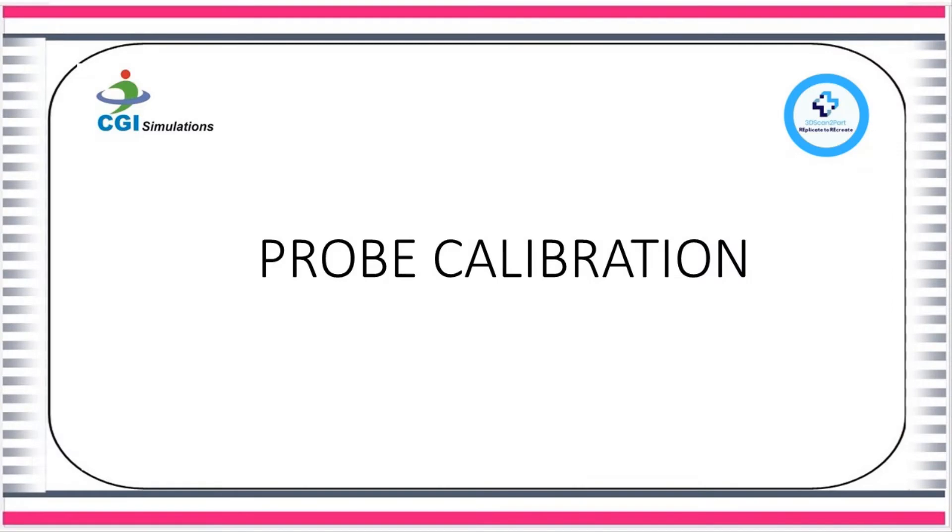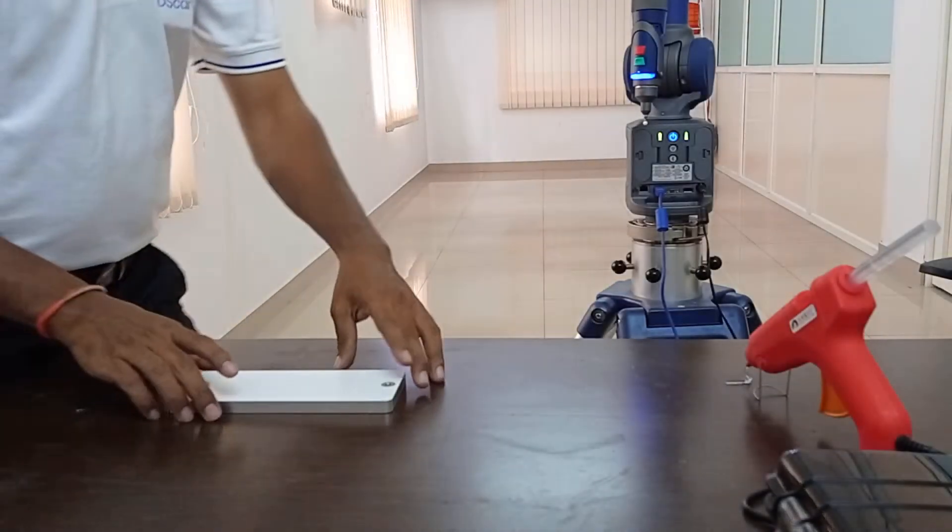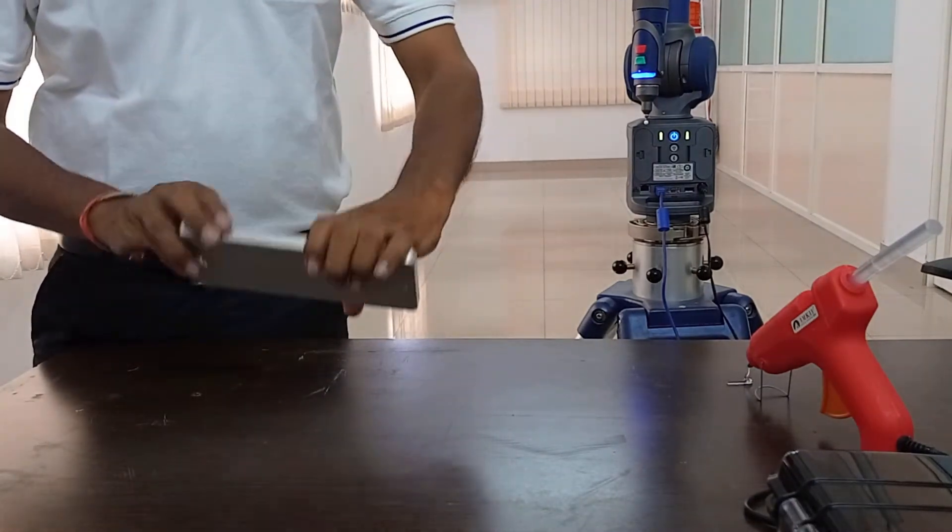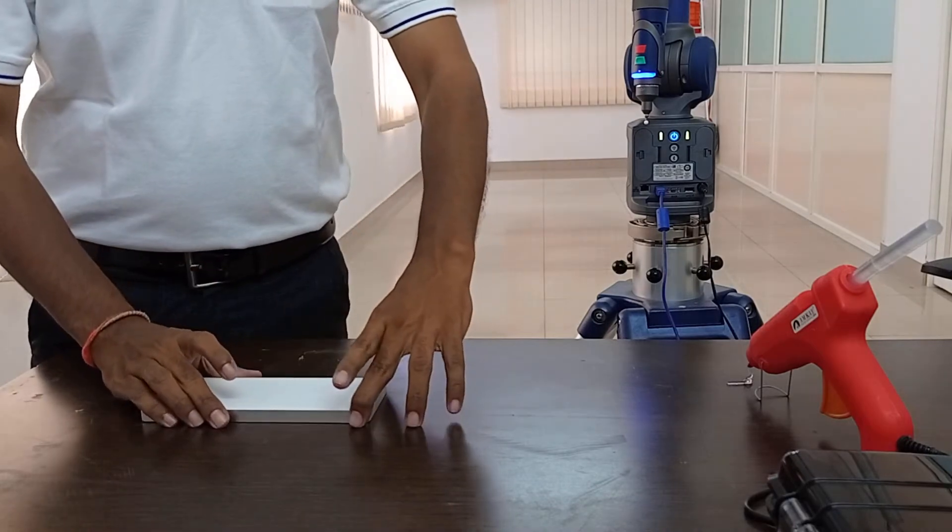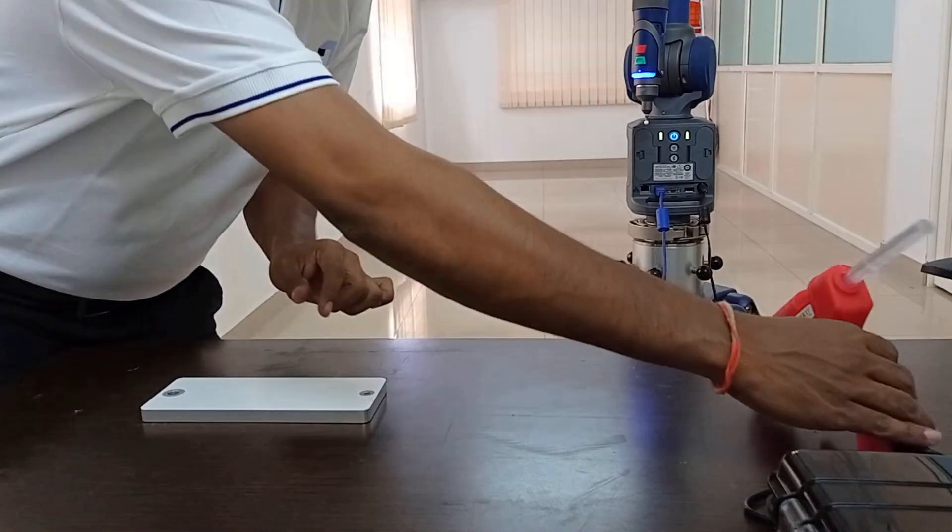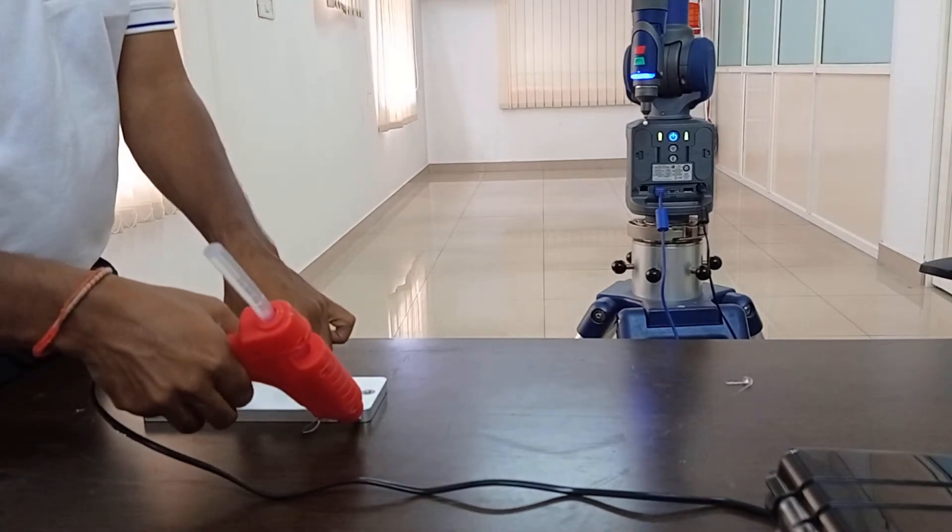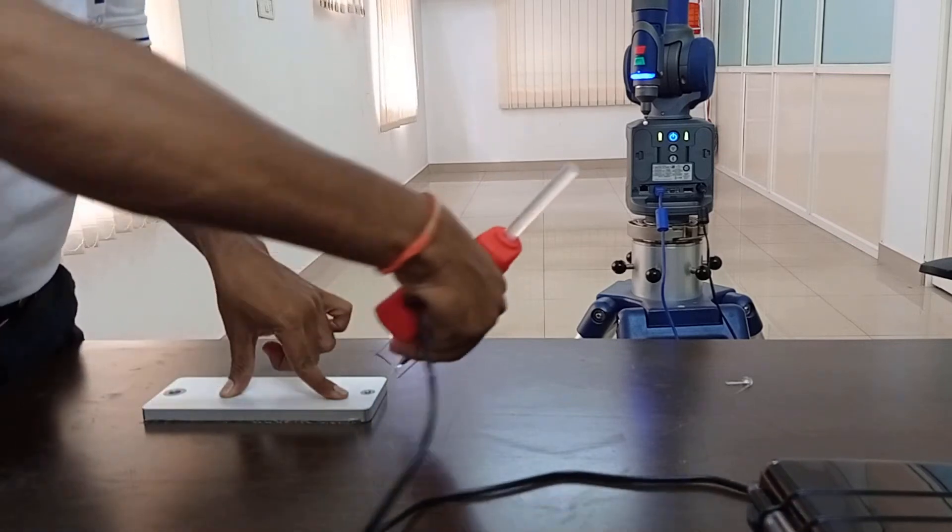Before starting any inspection project we should always compensate the probes so that we get the accurate results. Before using the calibration or compensation plate assure the underside of the plate and the surface it will be placed on are clean and free of any debris. We are using glue gun to stick the calibration plate to the surface. Any component that has to be inspected should be rigidly fixed to the surface.